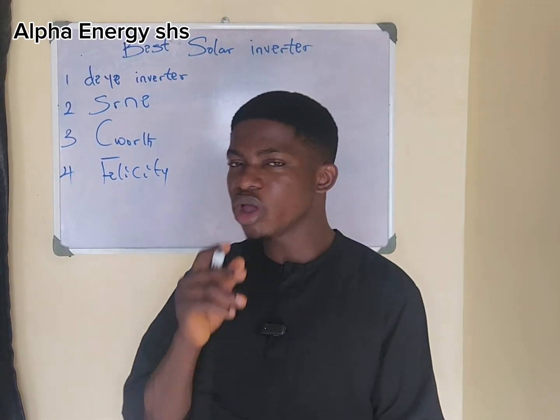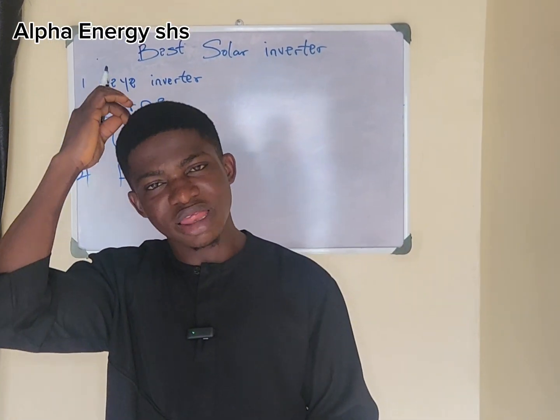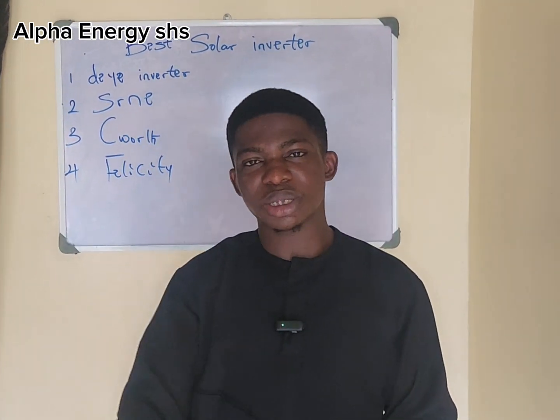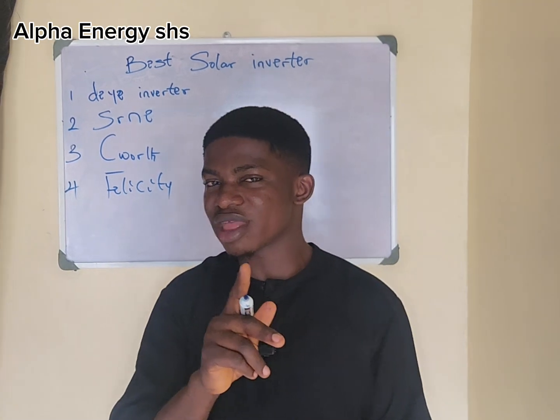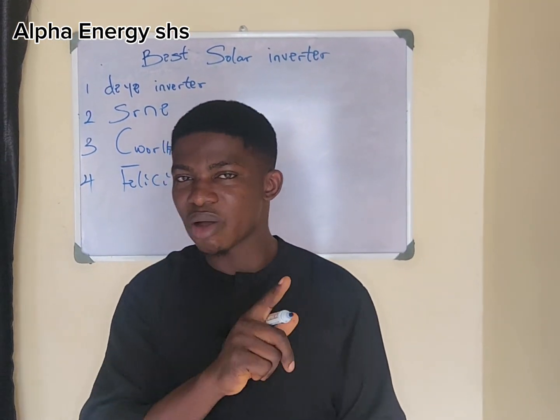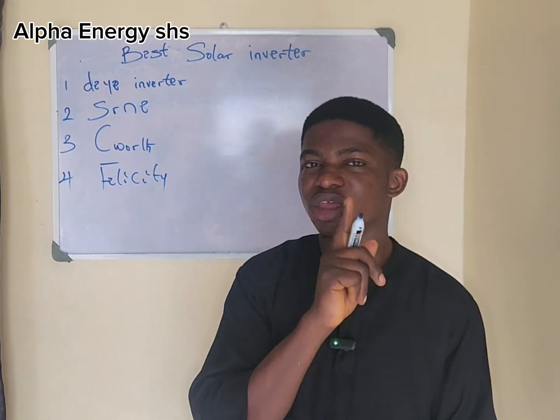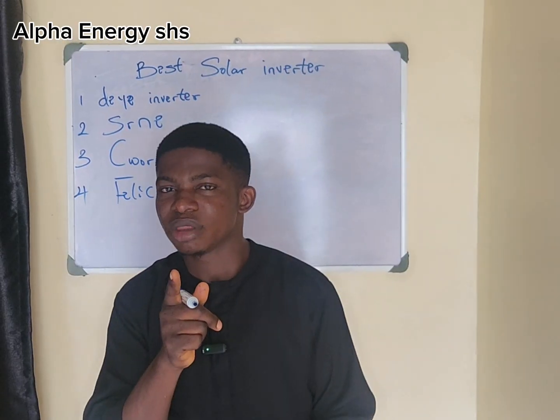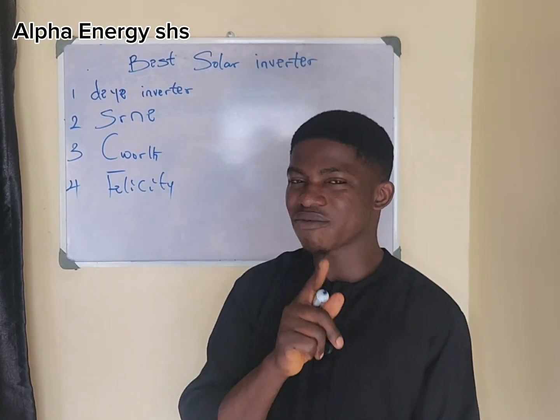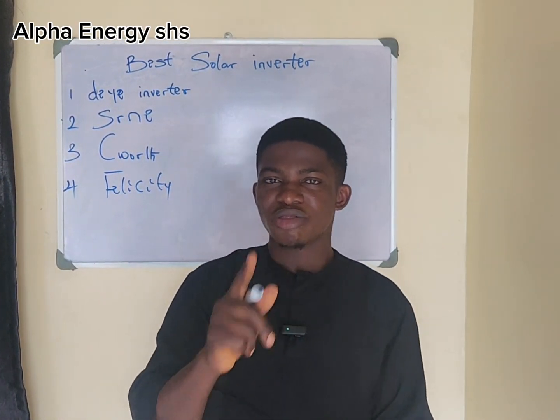Like today, I'll be going to a client's house. They say the inverter is not charging. I believe it's not from the inverter, because the inverter has been working very, very well. I think it should be from the DC breaker. The DC breaker I put there was 16 amps, so I'm very sure that breaker is bad. So I need to go change it.